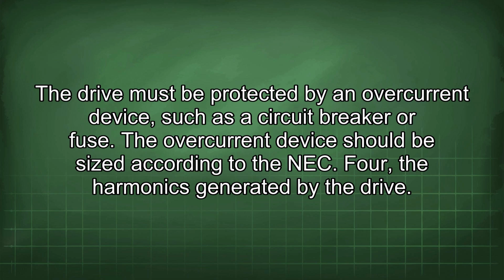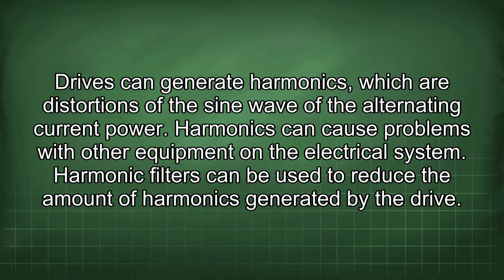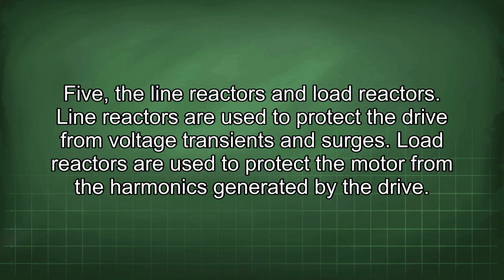Four: the harmonics generated by the drive. Drives can generate harmonics, which are distortions of the sine wave of the alternating current power. Harmonics can cause problems with other equipment in the electrical system. Harmonic filters can be used to reduce the amount of harmonics generated by the drive. Five: the line reactors and load reactors. Line reactors are used to protect the drive from voltage transients and surges. Load reactors are used to protect the motor from the harmonics generated by the drive.